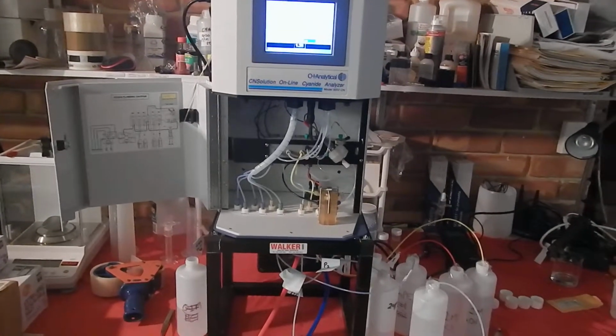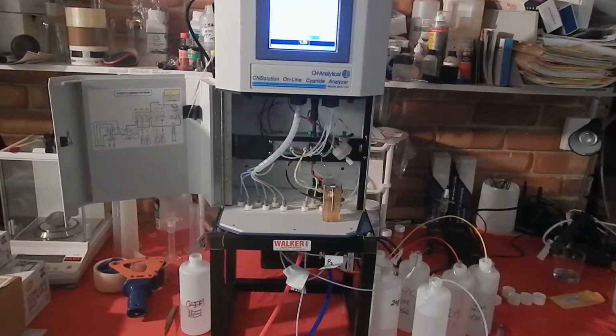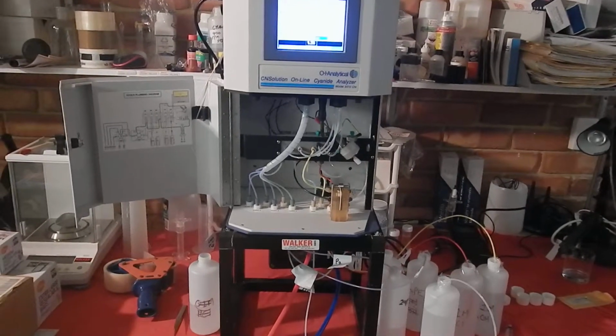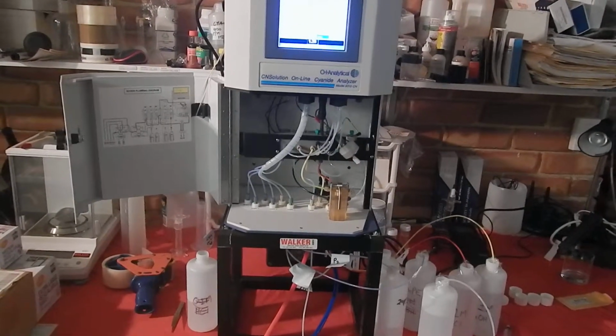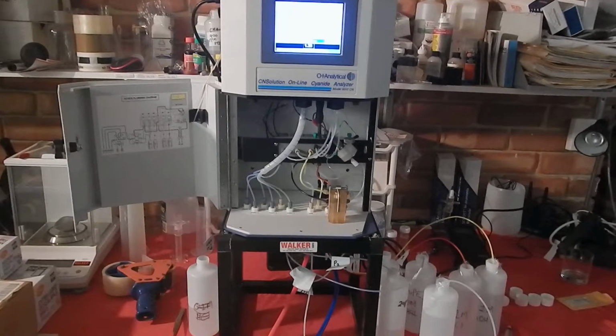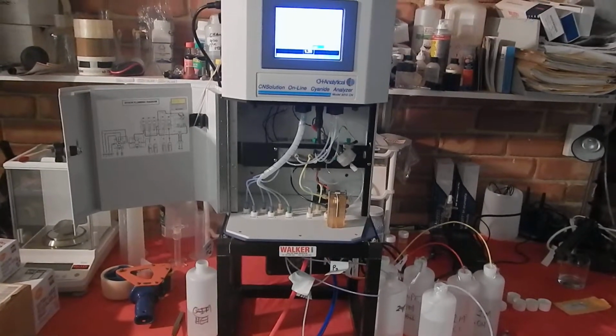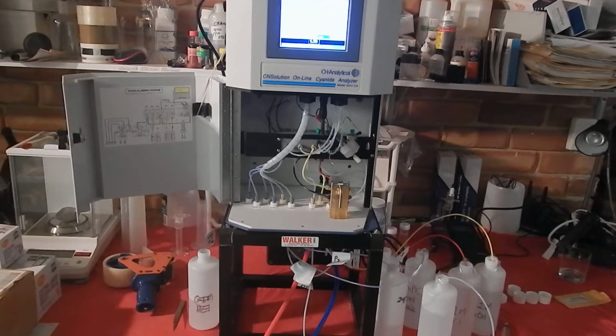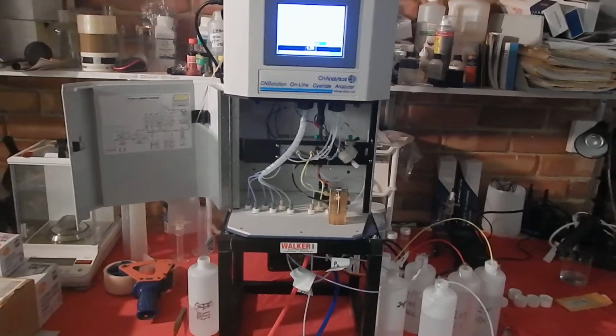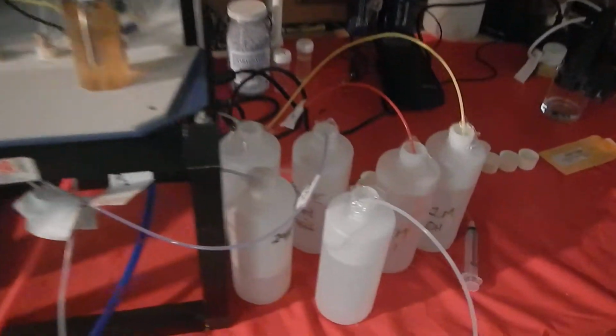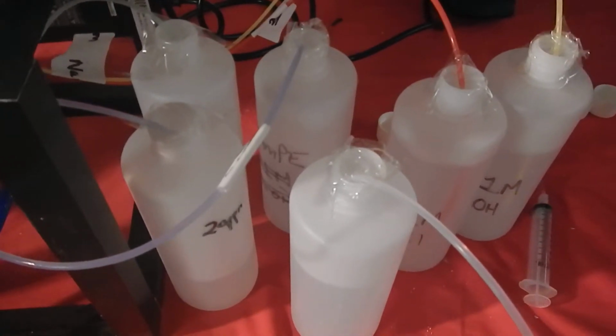I'd like to give you a small demonstration on how the OI Analytical 9310 Cyanide Analyzer, an online cyanide analyzer, works in the field. The principle of operation is gas diffusion amperometric detection. Essentially, starting from right to left, we run a series of eluents, standards and samples to the machine.